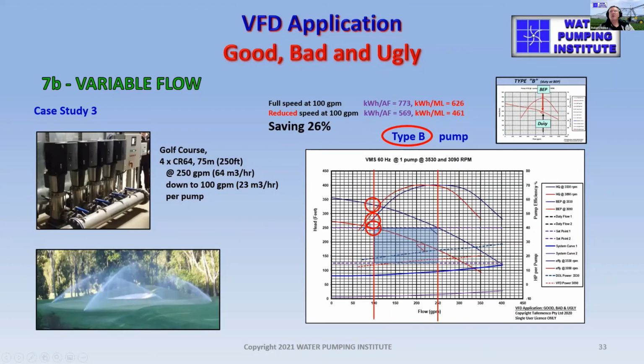What if we had a type B where the best efficiency point is at the duty point? We start off with a pump efficiency of 70%, and we finish up with an efficiency of 50%. So I'd call that a bad situation. Definitely not as good as it could be.